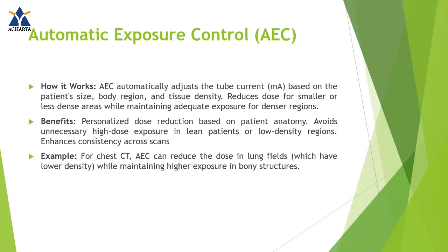Automatic exposure control software allows us to personalize the amount of mAs or amount of radiation given to the patient based on the patient structure, density of the organs, and how the patient is positioned, or the patient's anatomy, which allows us to avoid unnecessary exposure to a very high amount of radiation, especially when it comes to a lean or very thin patient. We don't have to give a high amount of radiation.